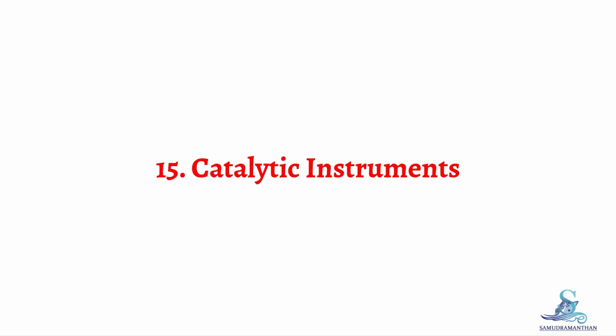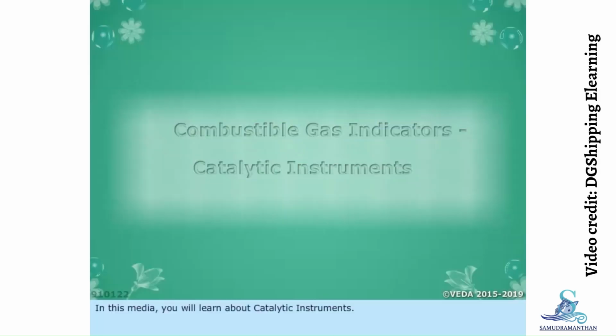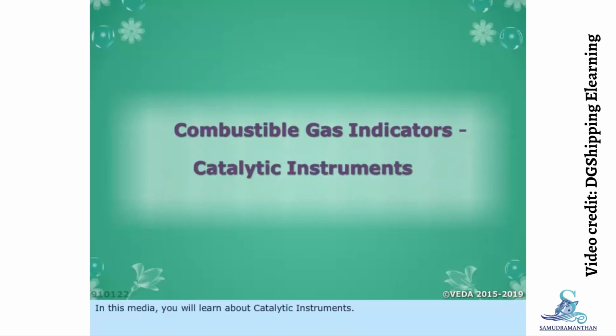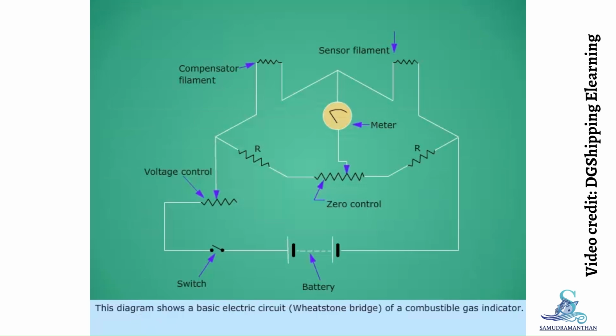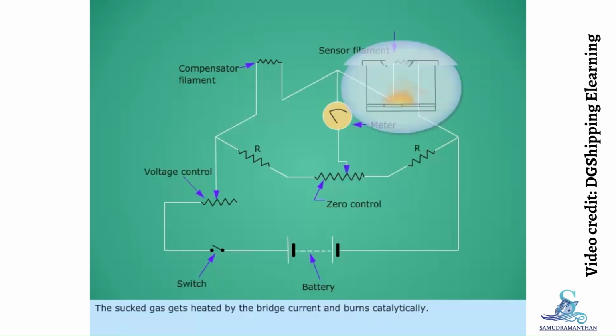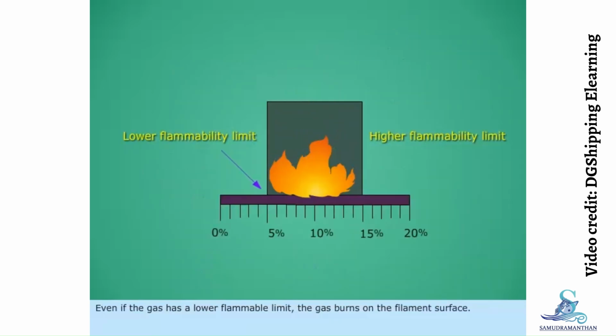Topic 15: Catalytic Instruments. In this media, you will learn about catalytic instruments. This diagram shows a basic electric circuit, a Wheatstone bridge, of a combustible gas indicator. The sensor filament of the combustible gas indicator sucks the gas. The sucked gas gets heated by the bridge current and burns catalytically. Even if the gas has a lower flammable limit, the gas burns on the filament surface.